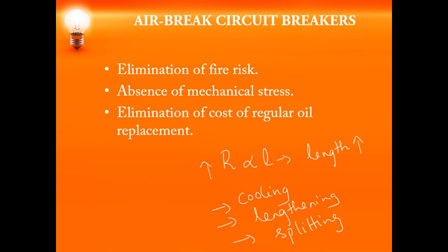By lengthening the arc, by splitting the arc, or by cooling the contact area we can obtain high resistance. These are the methods used to quench the arc in air break circuit breakers. The arc resistance is increased to such an extent that the voltage drop across the arc becomes more than the system voltage, and the arc quenches at the current zero of the AC wave. Air break circuit breakers are usually used in DC circuits and AC circuits up to 12 kV.